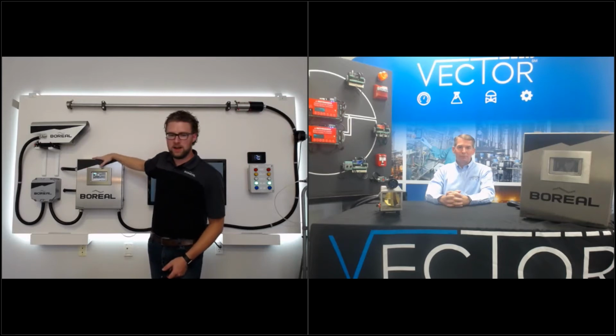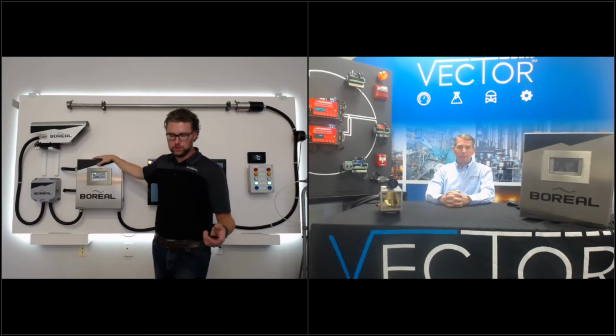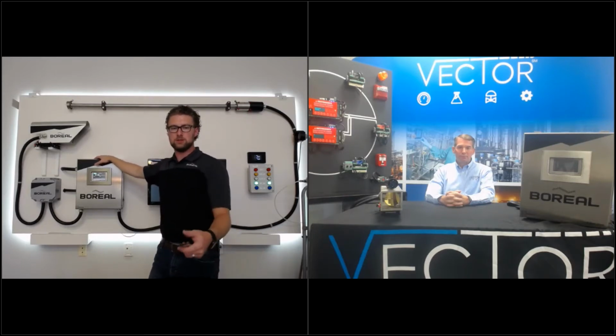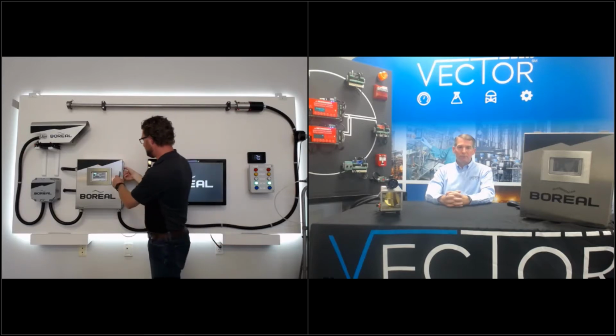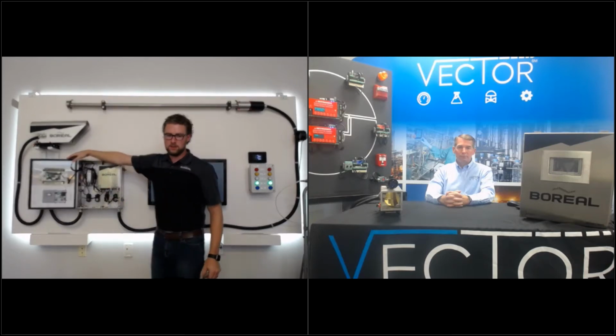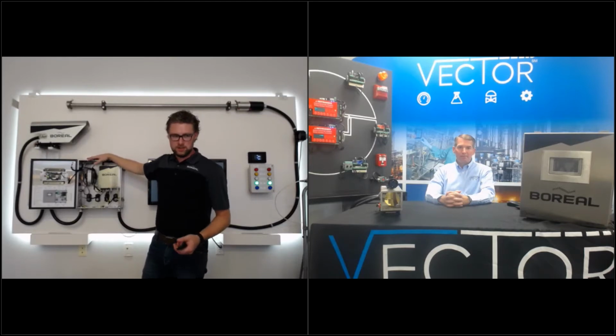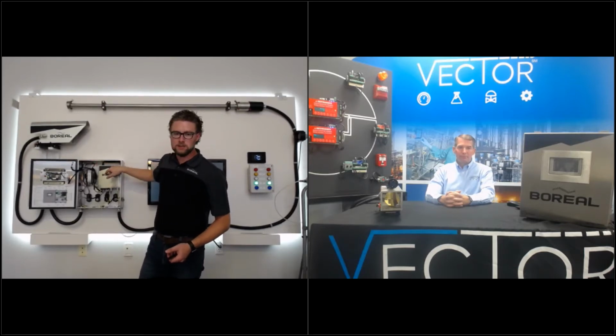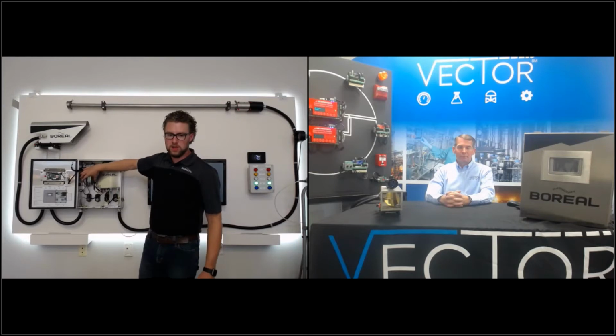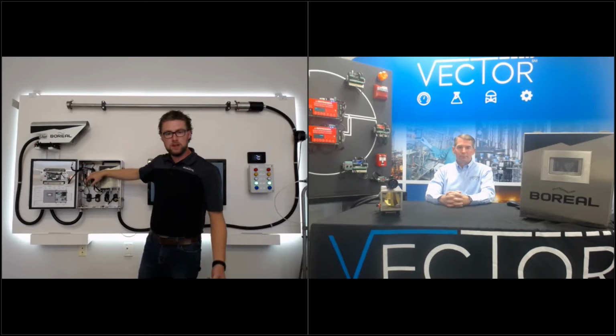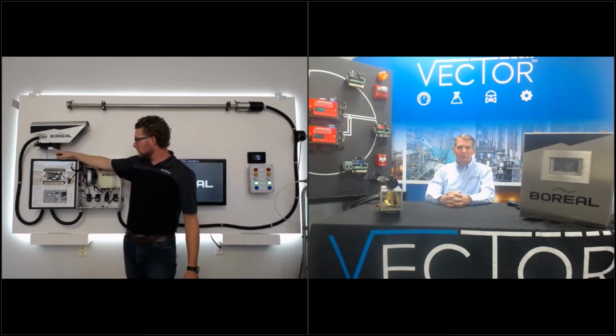What we have here is our analyzer enclosure. This is fully suitable for a hazardous area environment. It is SIL suitable as well, so it can be integrated into your SIS. Inside of this enclosure, it is very easy to install and integrate into your system. We have the laser analyzer module, which houses the laser and all the control electronics. We have our power and communication termination section, so you run your 24 volt DC, you have your HART output communication, your relay outputs, Modbus, whatever have you. Down at the bottom is where we connect all of our measurement heads.